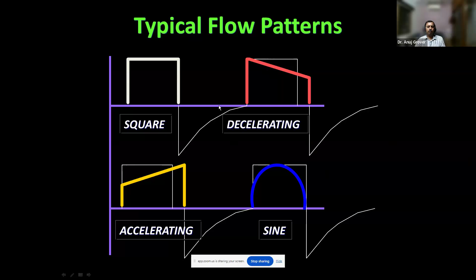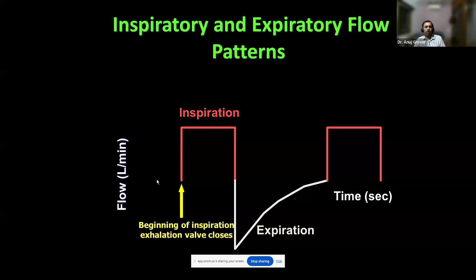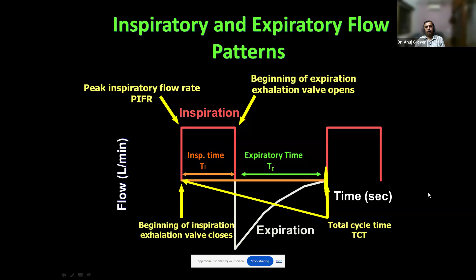Remember from the physics of mechanical ventilation you would have learned yesterday, when the exhalation valve closes, the flow begins towards the patient, and that starts the inspiration. It reaches the peak inspiratory flow rate, and after a set inspiratory time, the exhalation valve opens, and the flow goes the other way. That is the inspiratory time. Once the flow goes down, it reaches the peak expiratory flow rate, and then it goes back to zero. This is your expiratory time, inspiratory time, and the total cycle time. This is how the flow pattern usually looks.